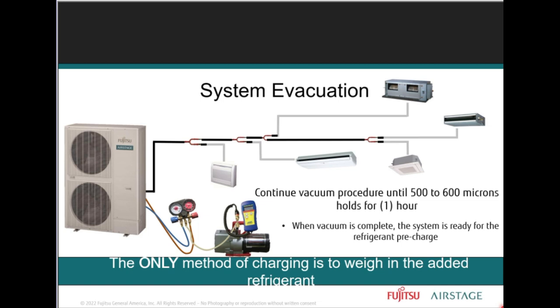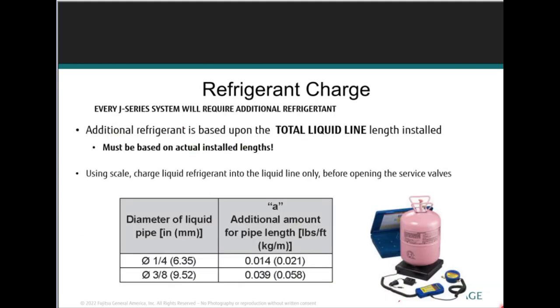The only method of charging is to weigh in the added refrigerant. So there are calculations that need to be done. There's no topping off. There's no superheat. There's no pressures you go by, especially on a Fujitsu system.